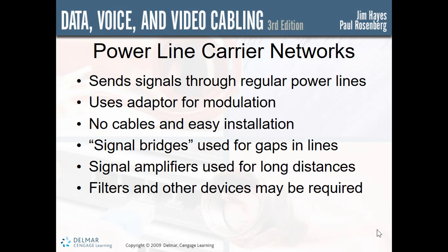The system imposes data signals right over the power line current, and the voltage and frequency differences are easily separated from each other by a tuned receiver. The power lines operate at 60 cycles per second and 120 volts, whereas data signals are normally in the 5-volt range and have a frequency of hundreds of thousands or millions of cycles per second. Now, power line carrier systems will never meet the technical performance of optical fiber cables or even other types of cables.